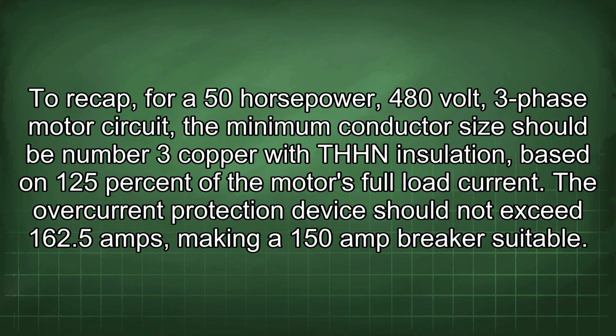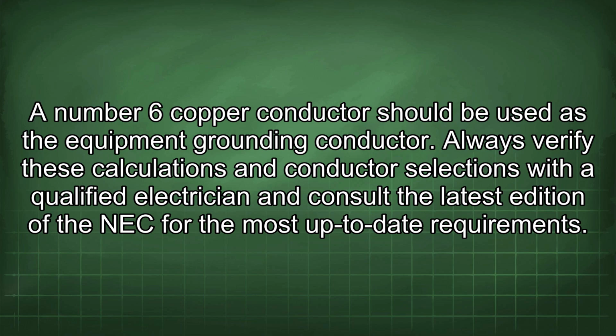To recap, for a 50 horsepower, 480 volt, 3-phase motor circuit, the minimum conductor size should be number 3 copper with THHN insulation, based on 125% of the motor's full load current. The overcurrent protection device should not exceed 162.5 amps, making a 150 amp breaker suitable. A number 6 copper conductor should be used as the equipment grounding conductor.